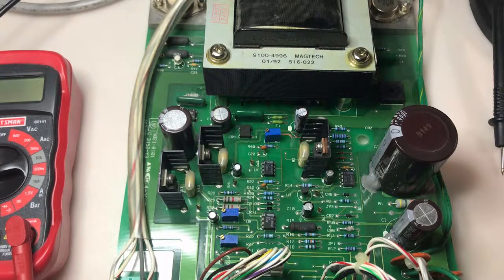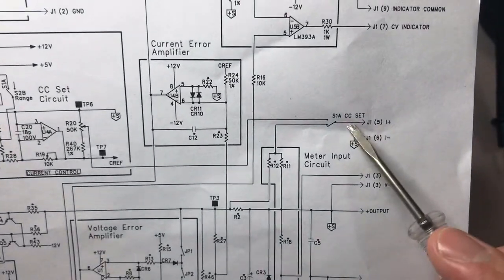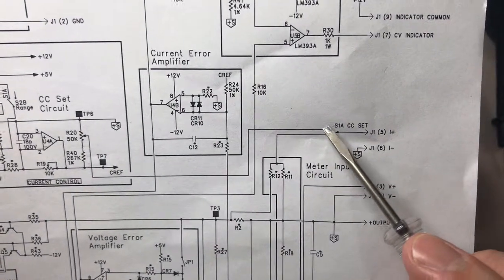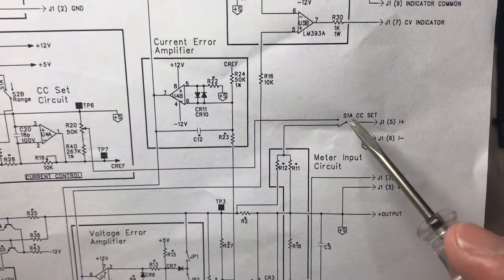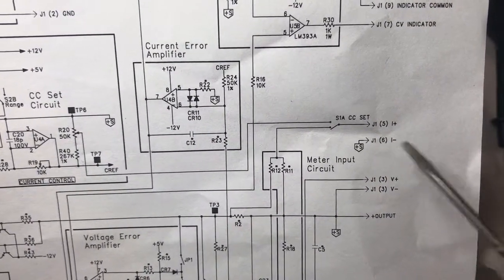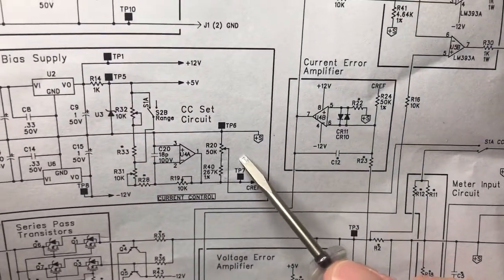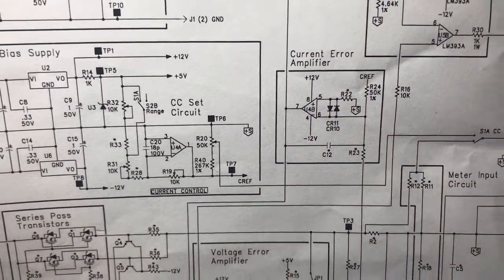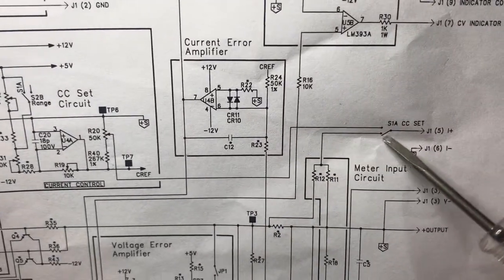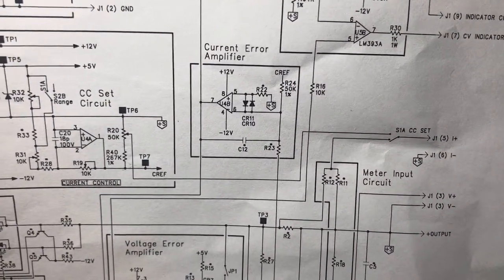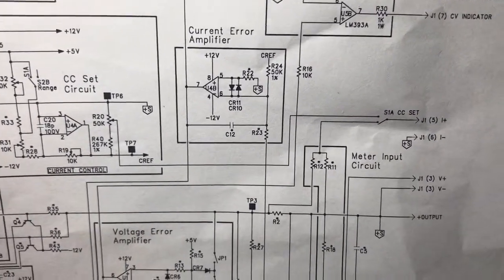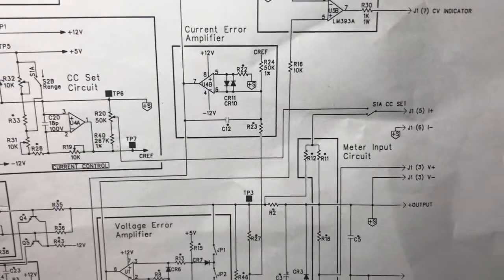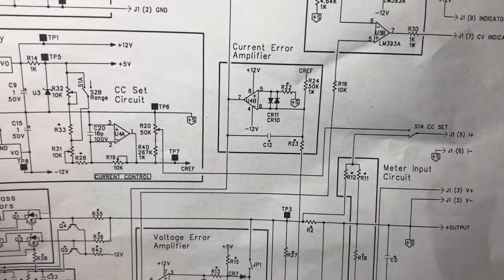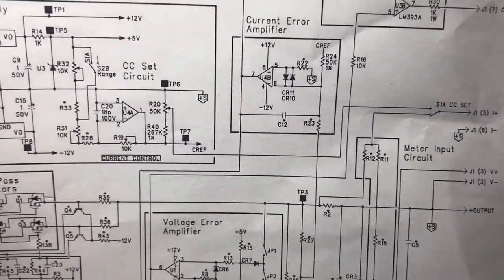I may have found the issue of why the constant current set point is reading abnormally, specifically reading above 0 when it should be 0. So if we take a look at the schematic, over here on the right, we'll see our constant current set point. When I depress the switch, it's in this upper position, and it's measuring between this pin and positive S. That's what it's measuring for that constant current. So let's follow it over here, and we're reading right off of the center tap of the potentiometer R20. So when I was adjusting R20, that's how I was able to get a 0 point reading here, which is good, but it did adjust my range. So my range no longer went from 0 to 500. When I was able to get it to read 0, it was like 0 to 100 or 200 maybe millivolt range. So that doesn't work.